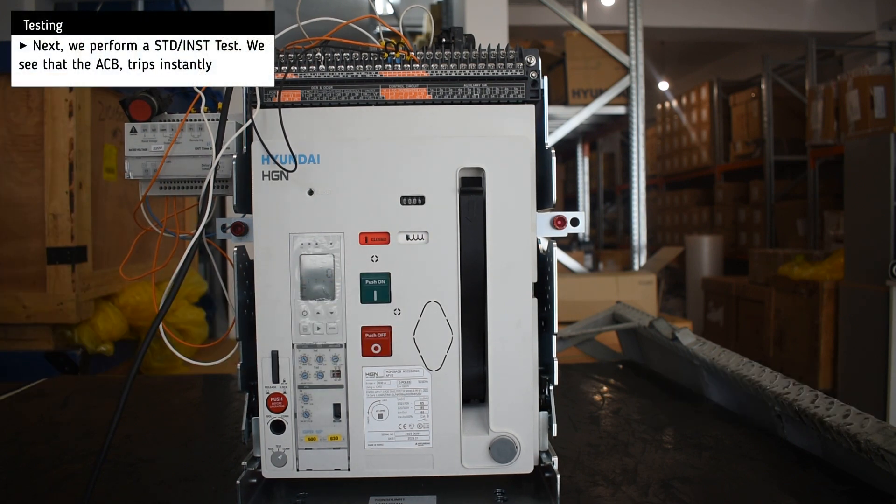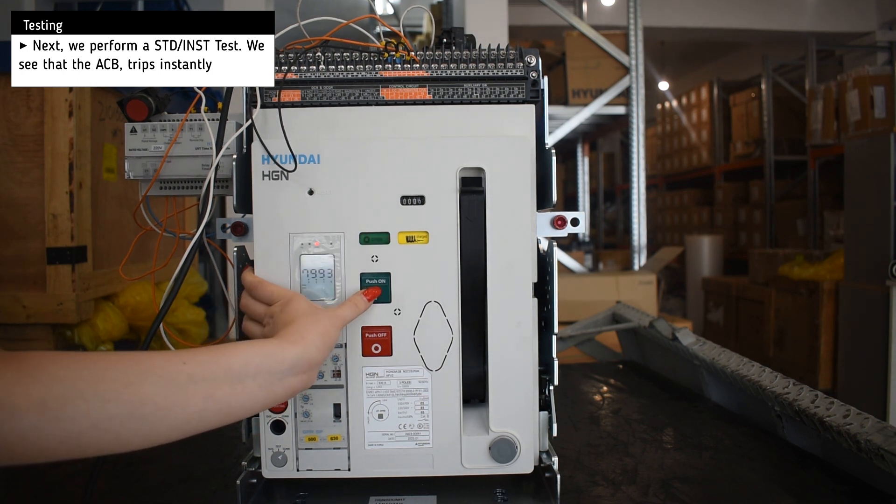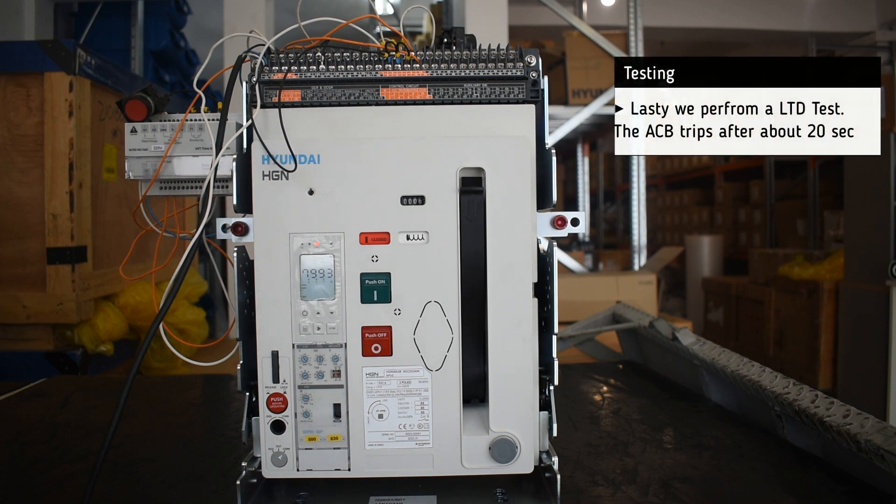Next, we perform a short time delay test, and the breaker trips almost instantly. Lastly, we perform a long time delay test.